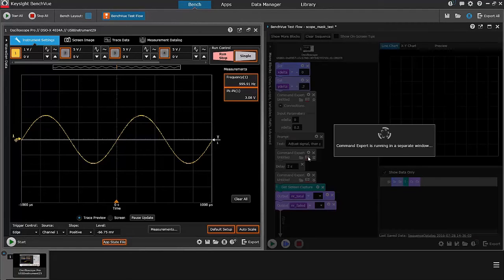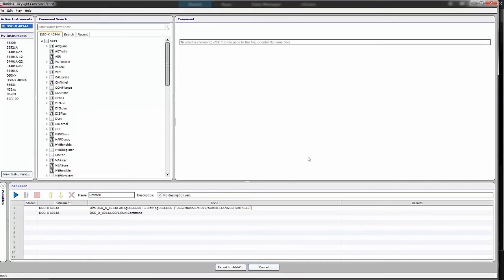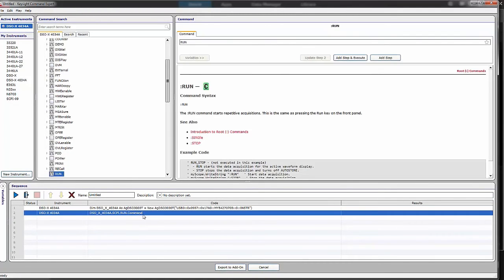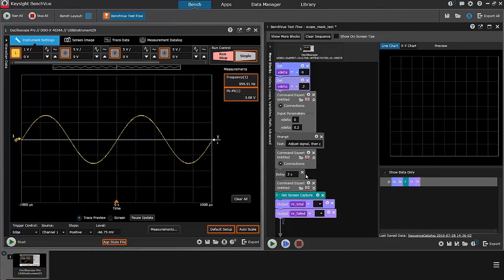Then, I call Command Expert again just to start the oscilloscope, so put it in run mode. In this case, the only command in here is a run command. When I'm done with that, I have to wait a couple of seconds for the actual acquisition to finish.